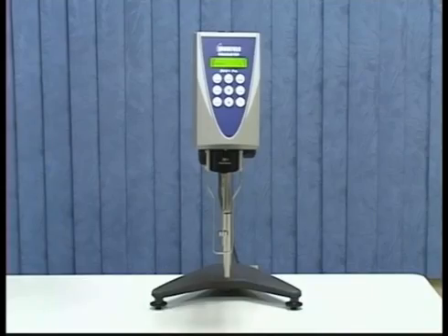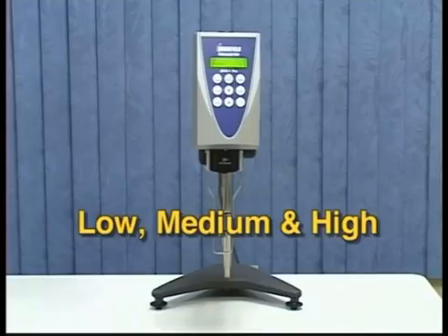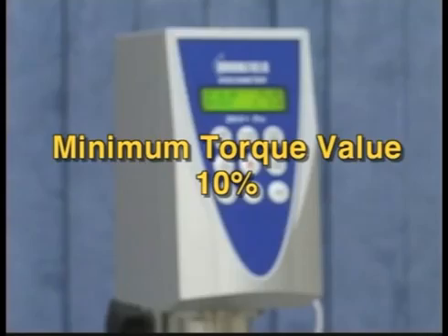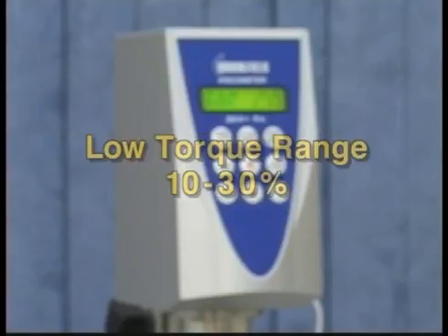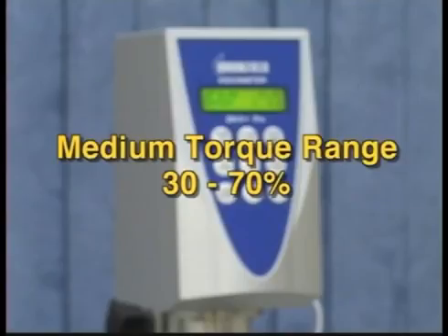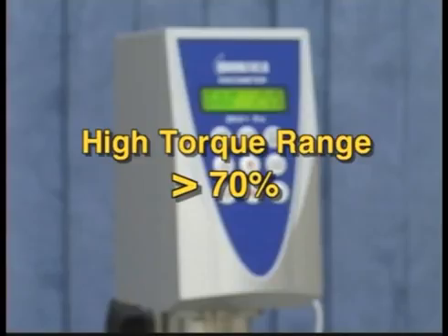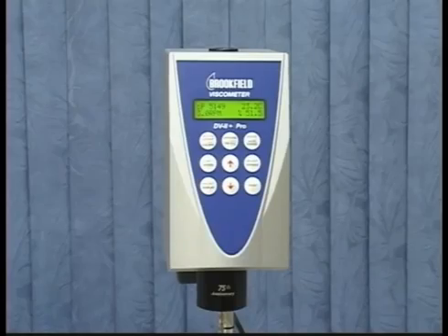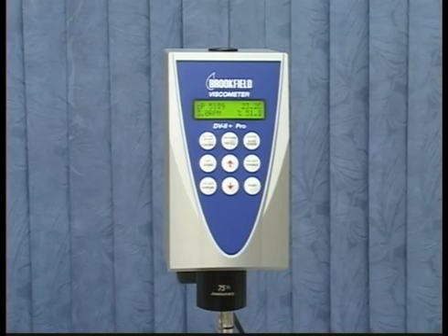Based on the spindle you will be using, select 3 speeds that will give you a low, medium, and high torque value. The minimum torque value for a good reading is 10%. A low torque range would be 10 to 30%, a medium range 30 to 70%, and a high torque range above 70%. This will check the linearity of the spring on this instrument through its full range.